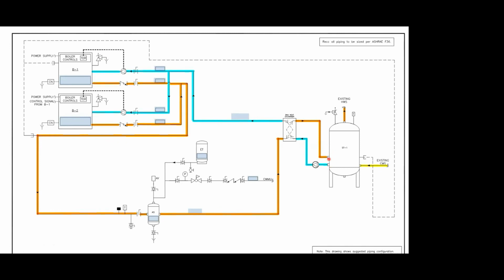Another way of doing it is having an integral coil inside your storage tank. I don't have a good example of that, but it acts just like a heat exchanger. It's a break. So your boiler water isn't directly in touch with the domestic. Okay. So in this case, you could say we're using a boiler to heat domestic water, but we're using a heat exchanger to separate it.